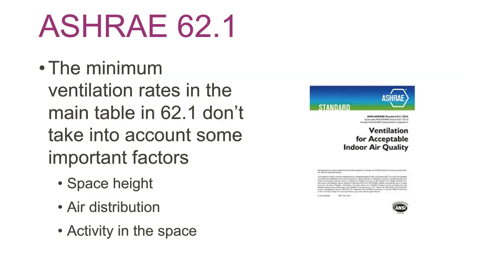But one of the major issues is that the amounts in the table don't take into account some pretty important factors. One of those is the height of the space. The table doesn't care whether the space is 6 feet tall or 50 feet tall. And that's not reality in the pools, because a lot of times you're delivering a fair amount of that air above the breathing zone to spectators, to wash windows, to wash the roof. And so a lot of that outside air is not getting to the breathing zone. And so the air distribution really needs to take that into account.